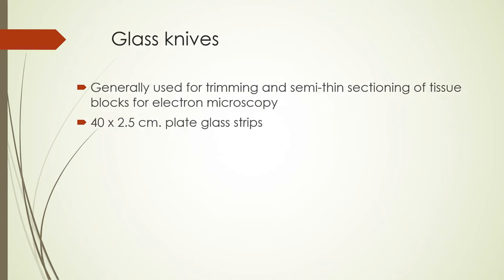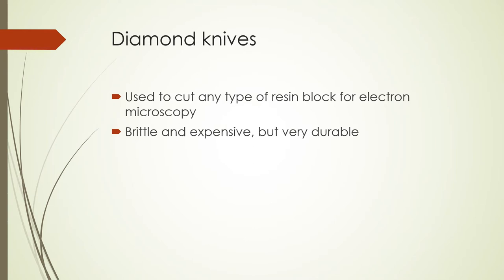Next we have glass knives, which are generally used for trimming and semi-thin sectioning of tissue blocks for electron microscopy. They are 40 by 2.5 centimeter plate glass strips — they look almost like cover slips but not in the same manner. Lastly, we have diamond knives, the most expensive type. They are used to cut any type of resin block for electron microscopy. They are brittle and expensive, but very durable.